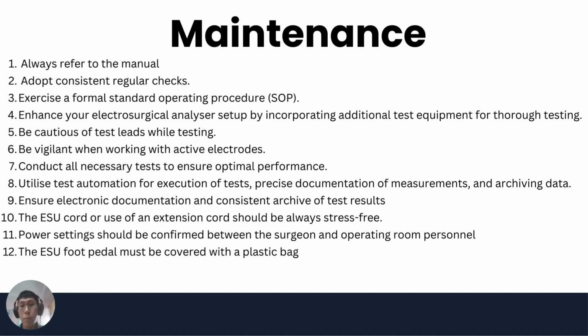Secondly, adopt consistent regular checks. If the manufacturer's service manual and inspection procedure are unavailable, it's necessary to establish the frequency of checks. Furthermore, many major electrosurgical device manufacturers suggest conducting semi-annual preventive maintenance tests to verify the unit's performance.